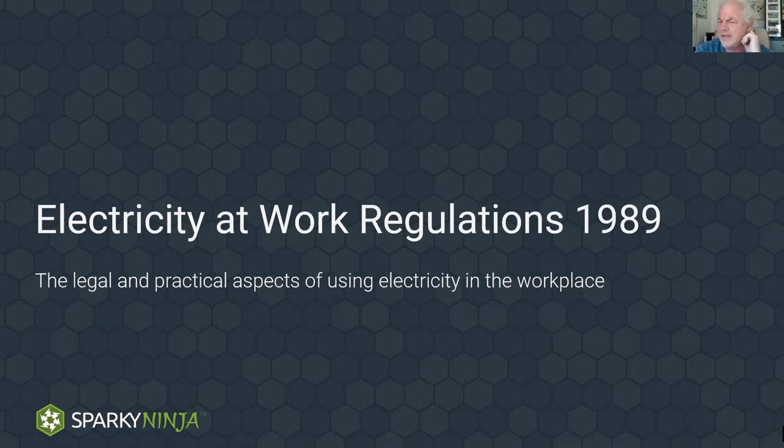Some of the issues we've been discussing over the last few months — especially to do with EICRs — when guys are scratching their heads thinking 'is this right, does it conform or not?', we've got to look wider than the Regs. Quite often when we look at the Electricity at Work Regulations or the Health and Safety at Work Act, they actually provide the answer to how we should be coding and treating an electrical installation. The Health and Safety at Work Act and Electricity at Work Regulations are law; BS 7671 is guidance, a code of practice.